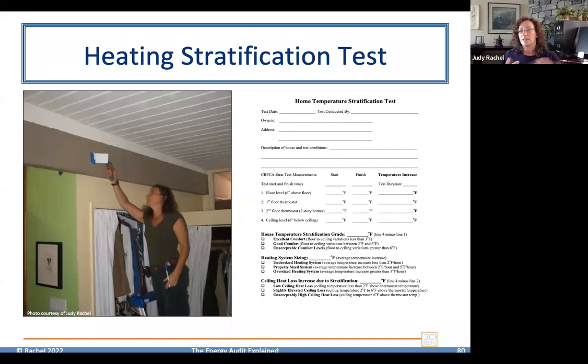It tells us about the system sizing. It can tell us whether a system is undersized or oversized for the house. And it tells us about the heat loss across the ceiling of the house, which tells us about the temperature differences and how well the air barrier is, if the air barrier is supposed to be at the ceiling level or not. And so therefore how much the heating system might drive infiltration through the house in stack effect.